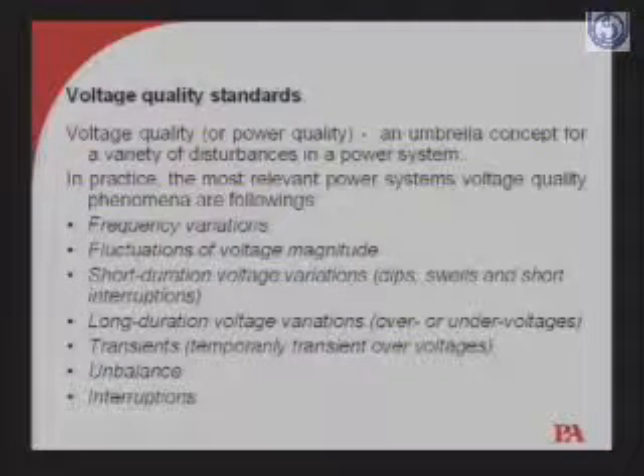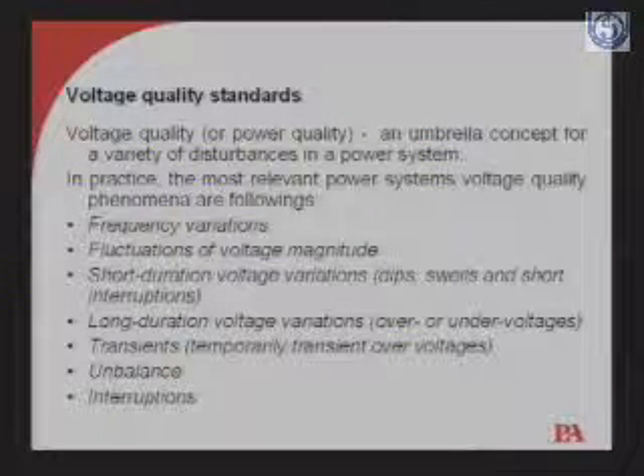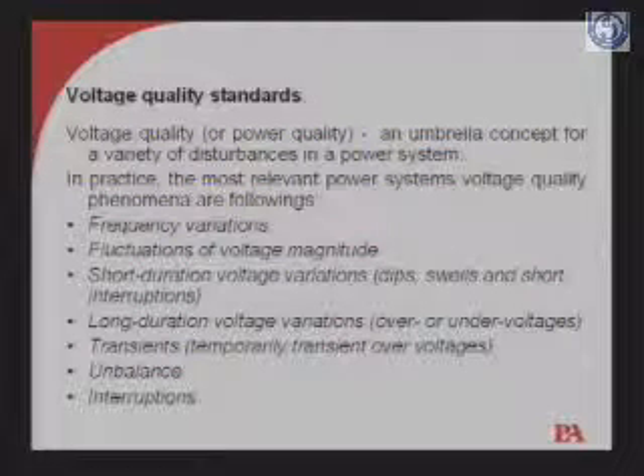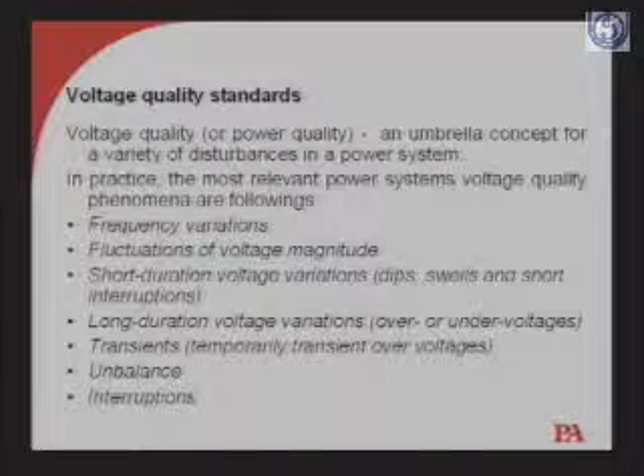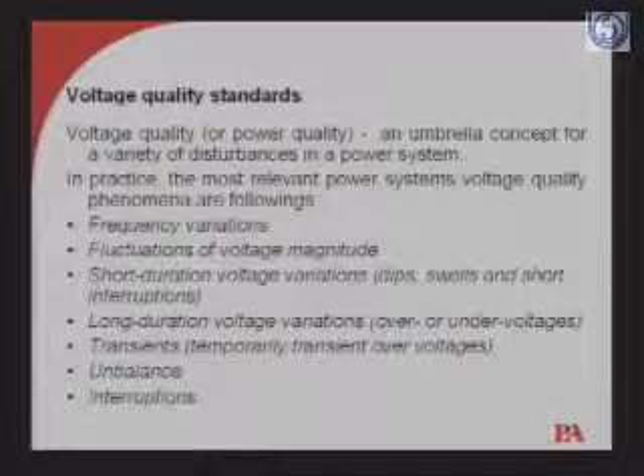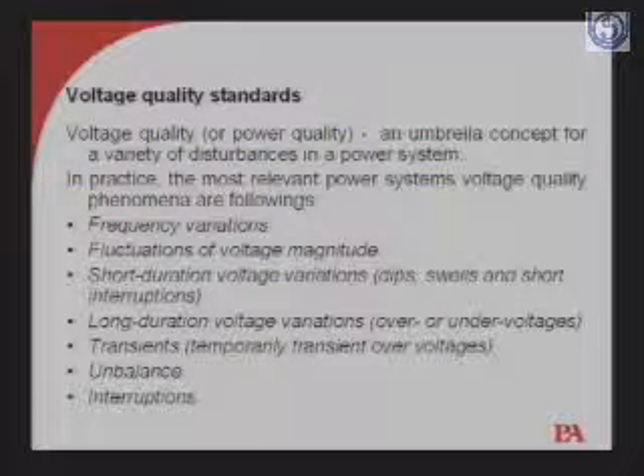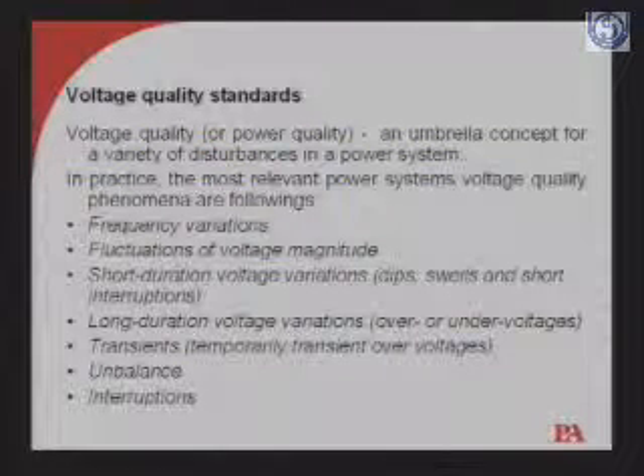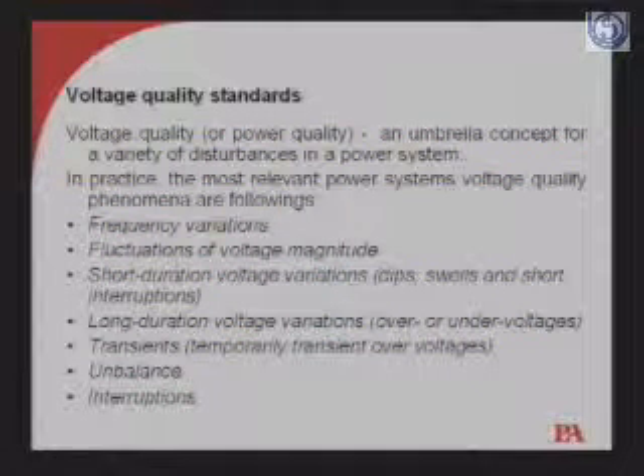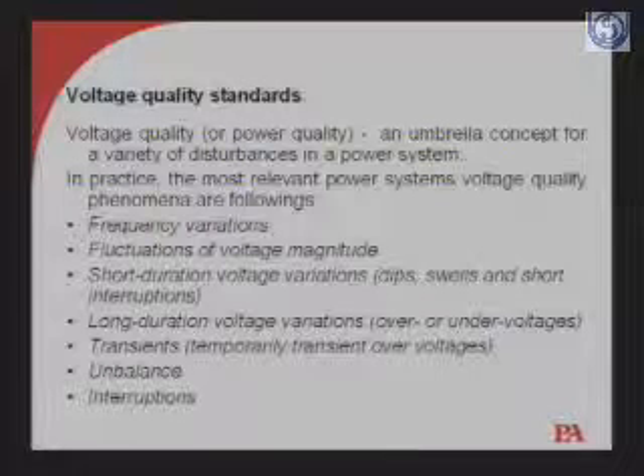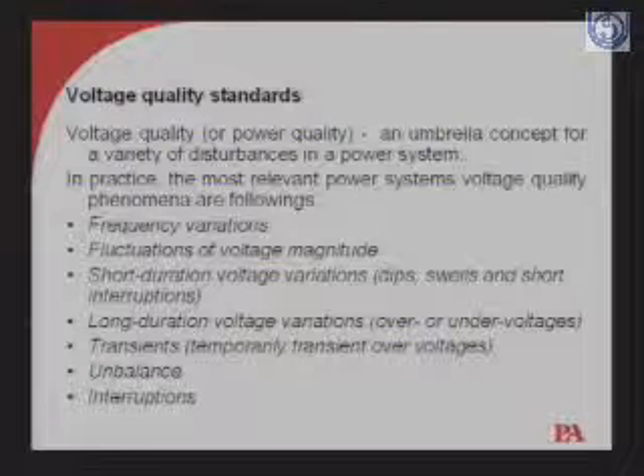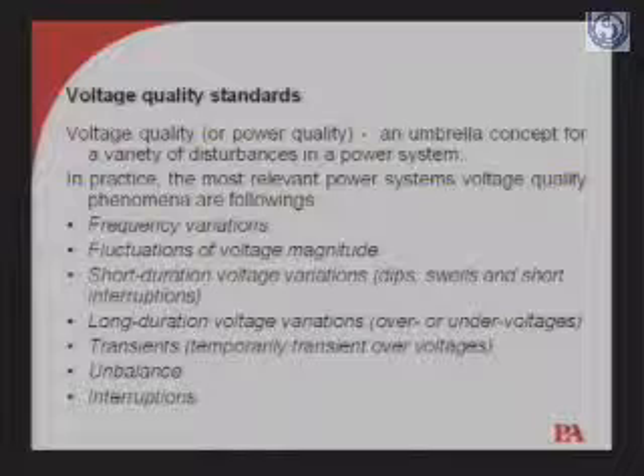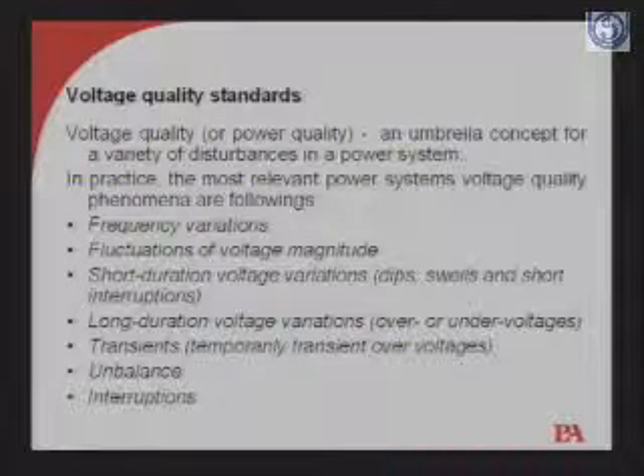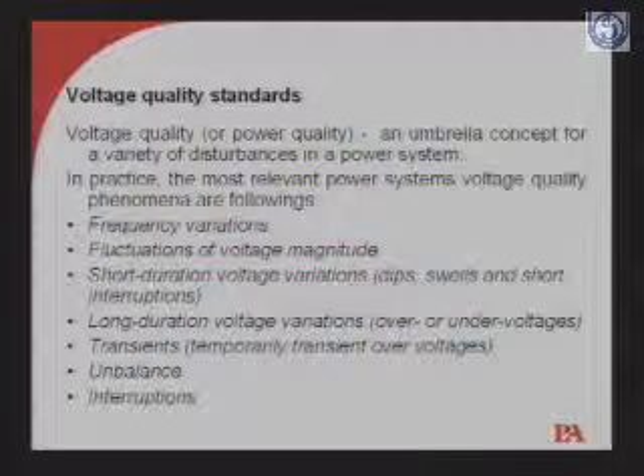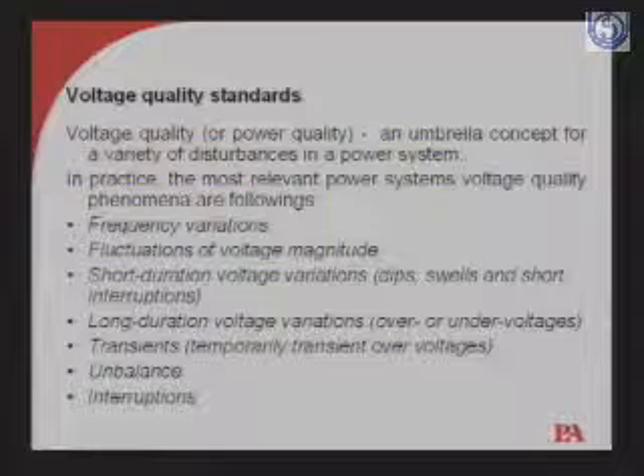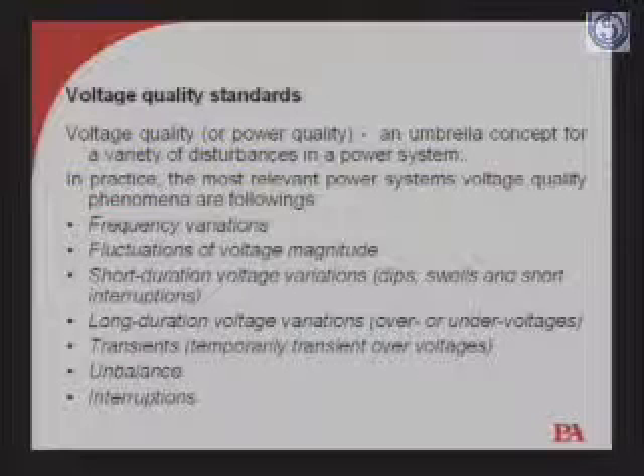So no fluctuation should be there. Short duration voltage variations: dips, swells, and short interruptions. If there is a heavy fault upstream in the system on another feeder, then there may be short duration voltage variations in this feeder, but it happens only when the earthing system is not proper, the system is not properly designed. So again, it is a controllable factor, and we should have one KPI in this regard as well. Similarly, long duration voltage variation, over or under voltages, is mainly because of network inadequacy. Over voltage happens for consumers who are near the source of supply. Under voltage affects those at the tail end of the network. Then transient, temporary over voltages, then unbalanced interruptions. These are the voltage quality standards.